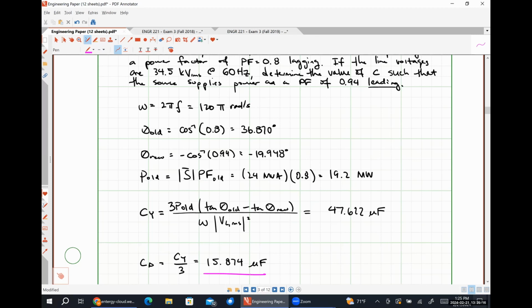It's all about the fact that the delta connected capacitor, while it uses a smaller capacitor, sees a larger voltage because it sees a line to line voltage, which will always be larger than the phase to neutral voltage, right? So effectively, it might use a smaller capacitor, but it has to be rated for a higher voltage, and that could potentially make it cost more. So realistically, you're always just going to look at both to see which one you can get for cheaper, and then that's what you're going to install. It's all about saving people money.